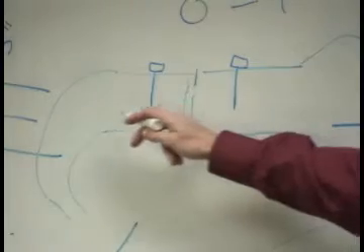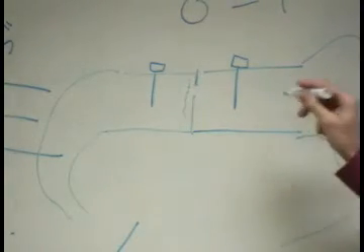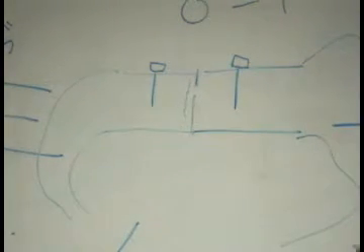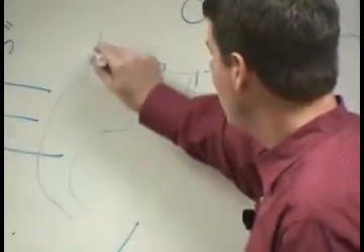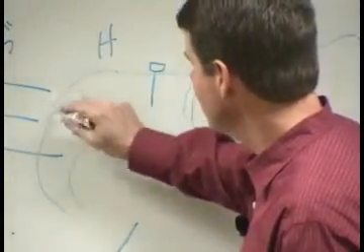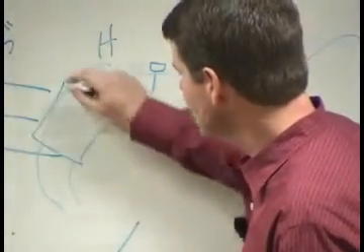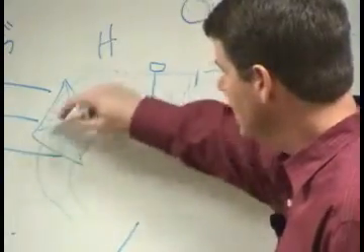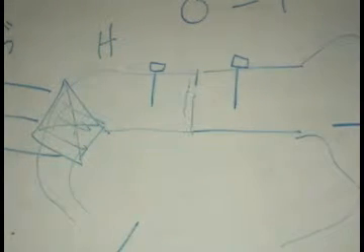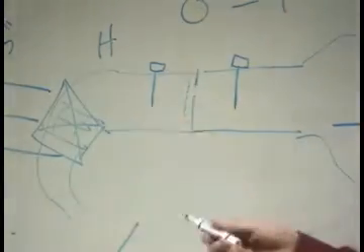So we actually have air flowing through that sensor, which means on the high side, we've got a filter to keep any of the lint and crud out of that orifice and out of that sensor, because otherwise, you know what the inside of the ducts look like. They just fill up with dirt over the years. So you've got to have that filter in there.